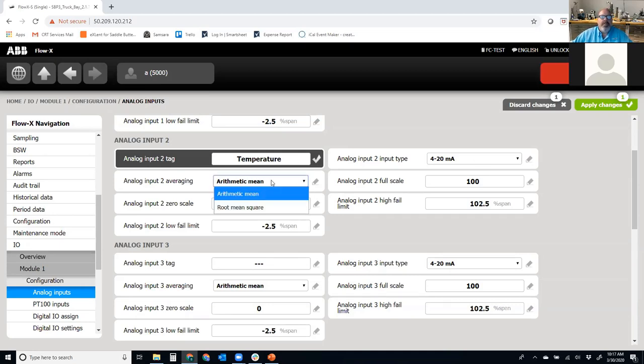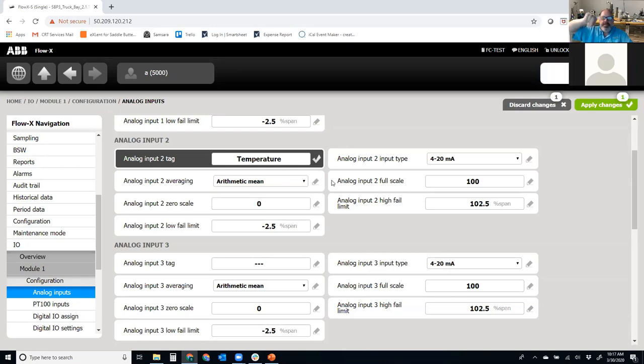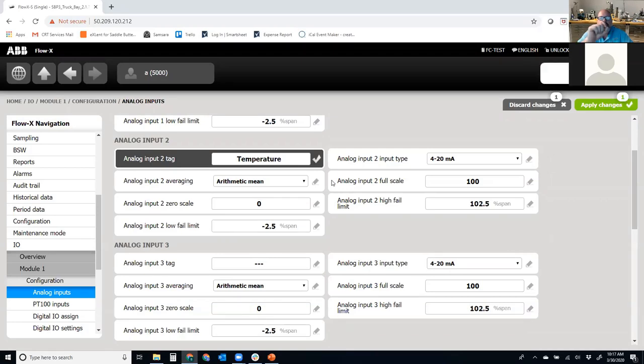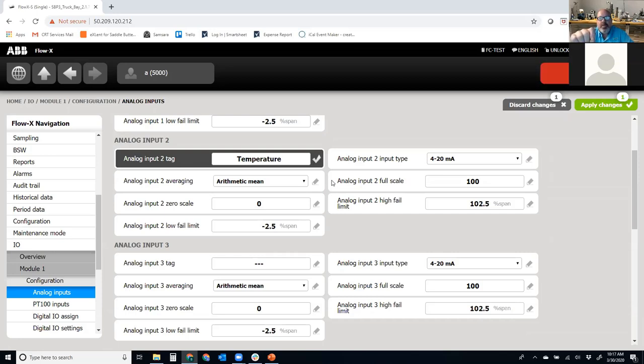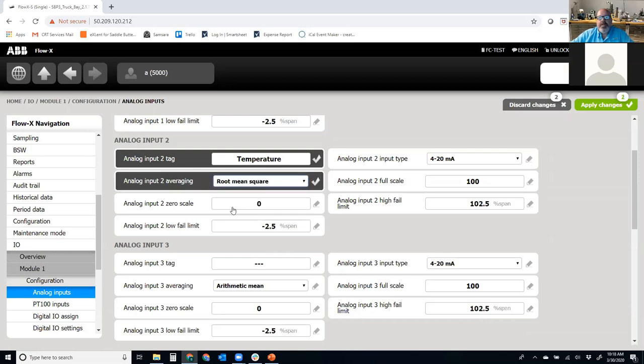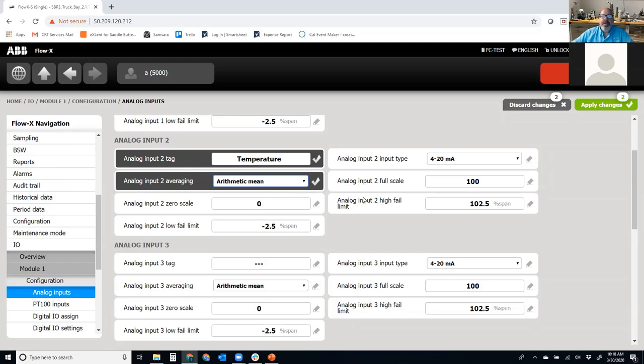So what this means is my starting point is going to be four milliamps. Four is going to be my starting point where when I go on my scale, my scale is 16 milliamps, because I subtract four from 20, that gives me 16 milliamps of range. We're going to use the arithmetic mean of averaging. That signal is changing a little bit. And if it's changing during the course of our processing, we do a little bit of an averaging because it's going to fluctuate.